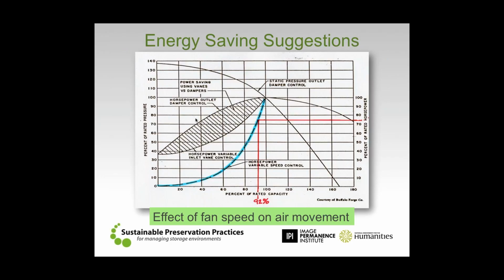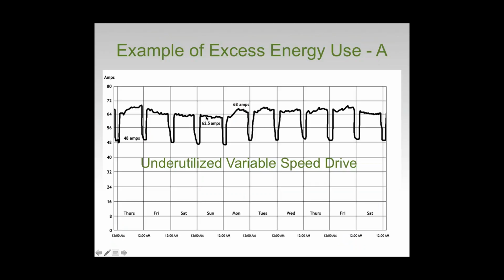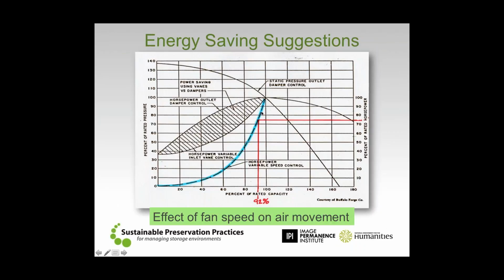As we start to reduce fan power, the good news is that we can maintain an awful lot of our total airflow in terms of how much air we're sending out to the space. But what that does in terms of the horsepower or the energy that we use is fairly significant. So here's our example where we just reduced the operation of the fan from the weekday operation down to the weekend operation. We reduced it by not quite 10%, right? So here we are. We've backed off on that fan speed by 10%, down to about 92.